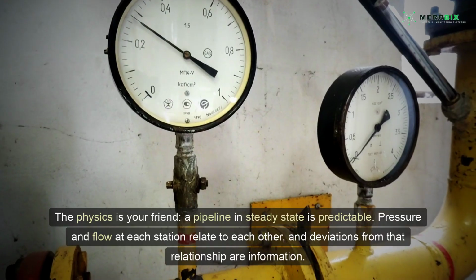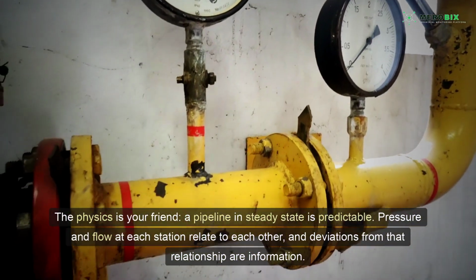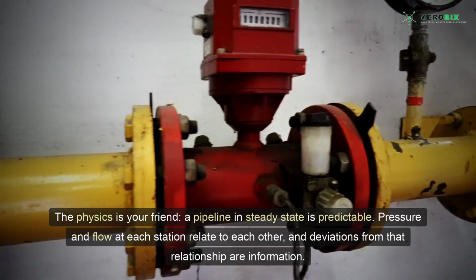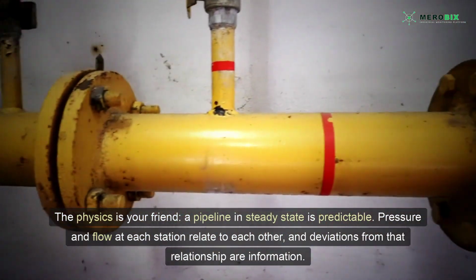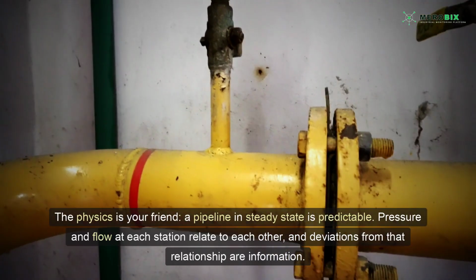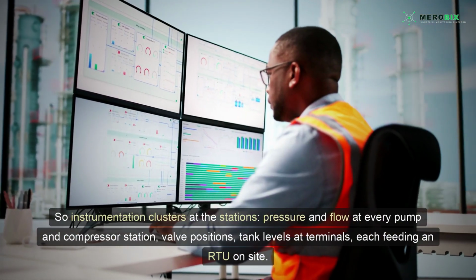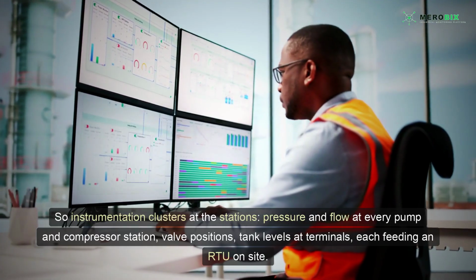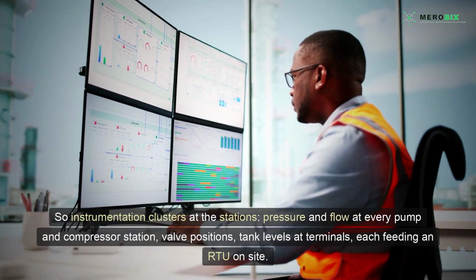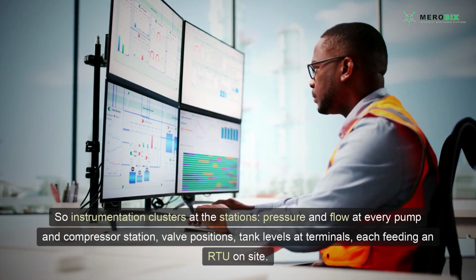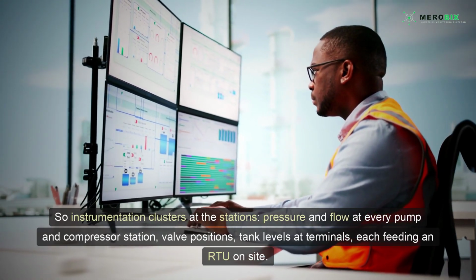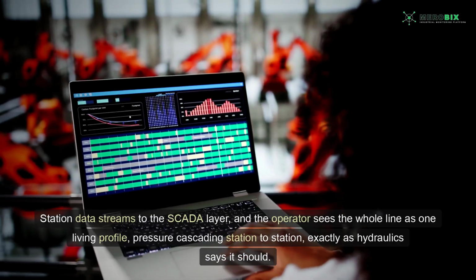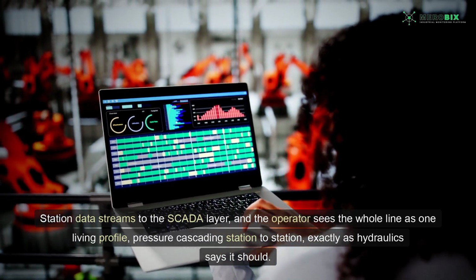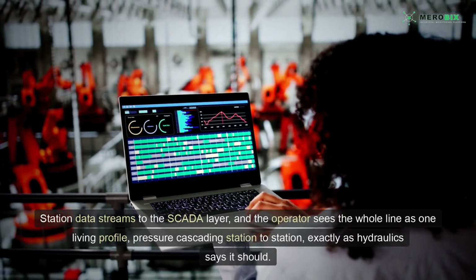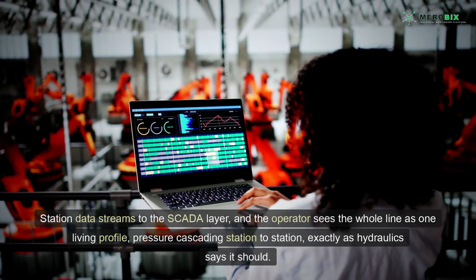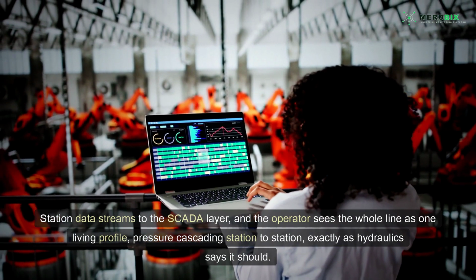The physics is your friend. A pipeline in steady state is predictable. Pressure and flow at each station relate to each other, and deviations from that relationship are information. So instrumentation clusters at the stations: pressure and flow at every pump and compressor station, valve positions, tank levels at terminals, each feeding an RTU on site. Station data streams to the SCADA layer, and the operator sees the whole line as one living profile, pressure cascading station to station, exactly as hydraulics says it should.